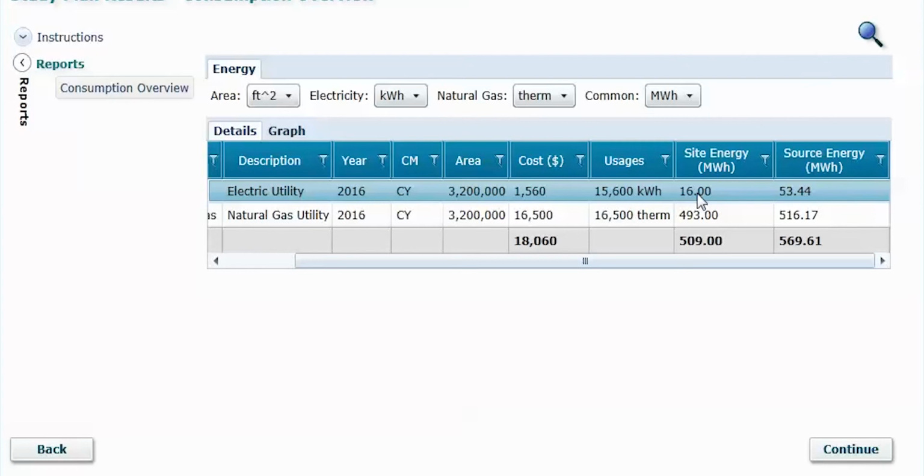Now it's not going to be an exact fit for a couple different reasons. One, they're not necessarily all exactly the same buildings. You may have, as I mentioned, this data for a whole installation, but only be looking at a small section. At the same time, even the data that's rolled up at this point that comes in from the bills is going to include a lot of additional energy usages beyond the buildings. Things like street lighting aren't associated with any given building, but it's still going to be part of what they're billed for.